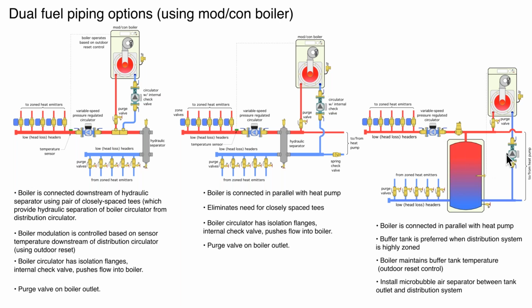And then finally, here's another connection. This is showing a buffer tank, a 3-pipe configuration. So again, you see whether the heat is coming from the boiler or from the heat pump, this is giving you that possibility for direct to load heat transfer. And the boiler in this case, as well as the heat pump, would be controlled based on the tank temperature. And then again, purge valves over here on the return side of these zones. So again, there's several ways to do it. These can all work. There's slight differences in them. No strong preference here.